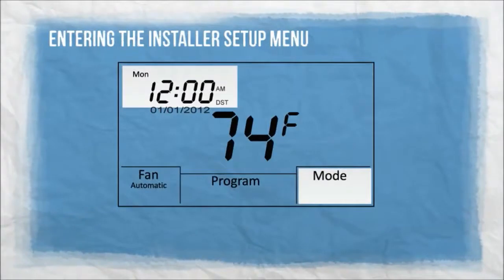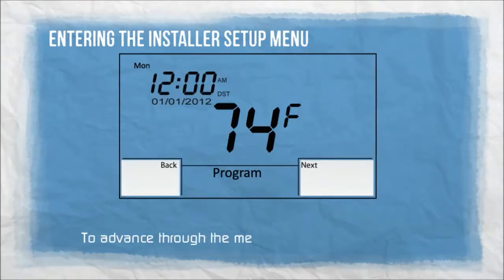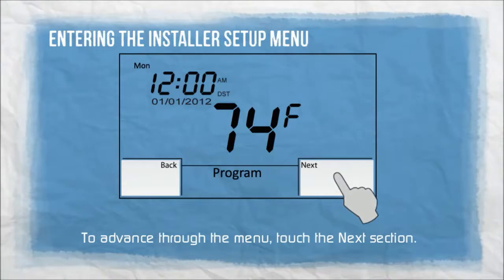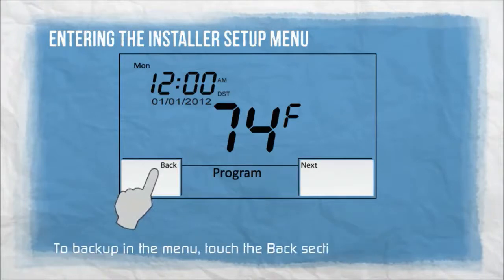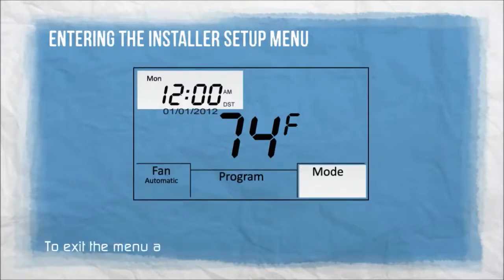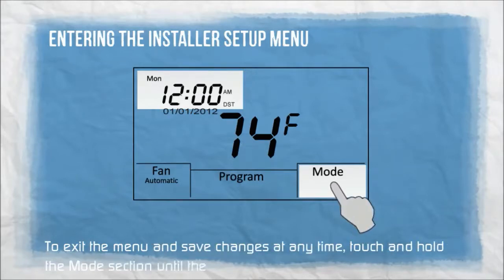Entering the installer setup menu: touch and hold both the clock and mode sections for 5 seconds. To advance through the menu, touch the next section. To back up in the menu, touch the back section of the screen. To exit the menu and save changes at any time, touch and hold the mode section until the display shows normal operation.